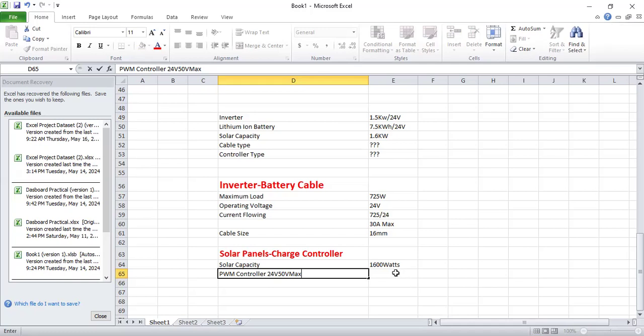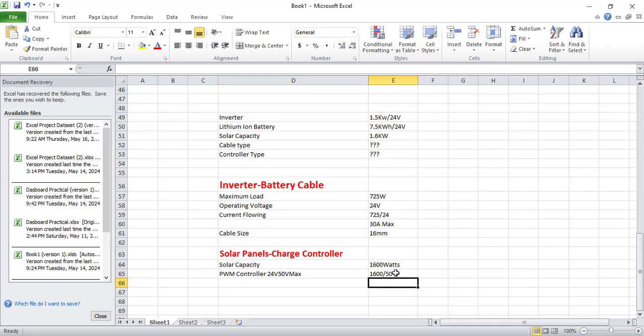For us to determine the cable sizing, we calculate 1,600 divided by 50 volts, which is the maximum PV voltage. If we do that, we get 32 amps. That's the current that will be flowing from my solar panel to my charge controller.